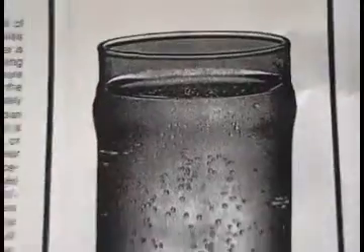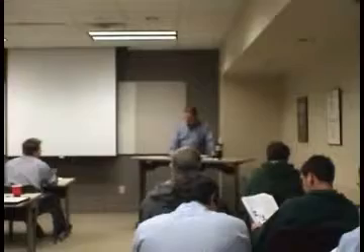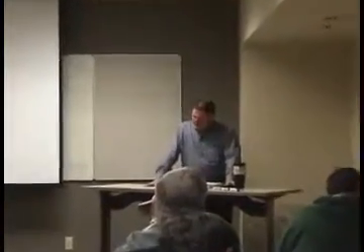Same thing happens in a hot water heating system, only there are more bubbles because there's more water. The bubbles are larger since the water is heated considerably above 70 degrees. It's impossible for bubbles to escape to the atmosphere in a closed system. If not controlled, the bubbles of air will travel through the system, causing gurgling noises and eventually become lodged in the radiation. As shown in the figure below, air can be trapped in the top of the boiler by using a dip tube.